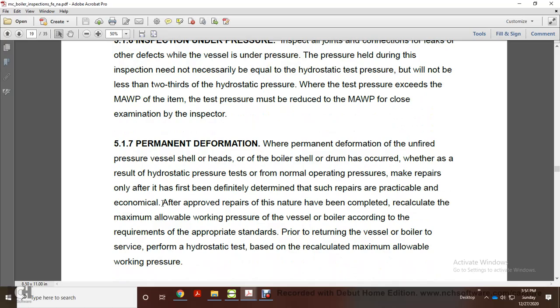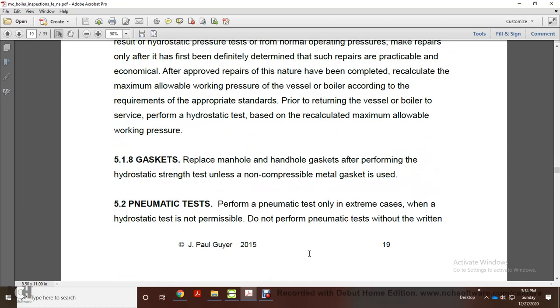5.17 Permanent deformation. If permanent deformation of an unfired pressure vessel shell, heads, or boiler shell or drum has occurred, whether as a result of the hydrostatic pressure or the normal operating pressure, make repairs only after it is definitely determined that such repairs are practical and economical. After approved repairs of this nature have been completed, recalculate the maximum allowable working pressure of the vessel or boiler in accordance with the requirements of the appropriate standard prior to returning it to service. Perform a hydrostatic test based on the recalculated maximum allowable working pressure.